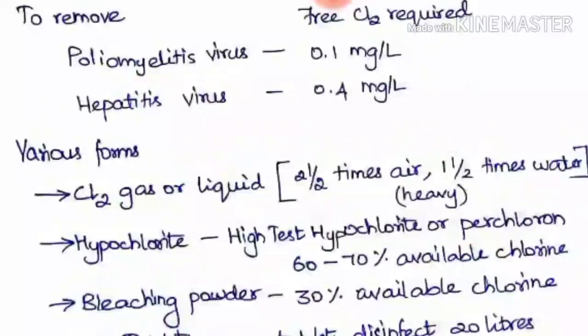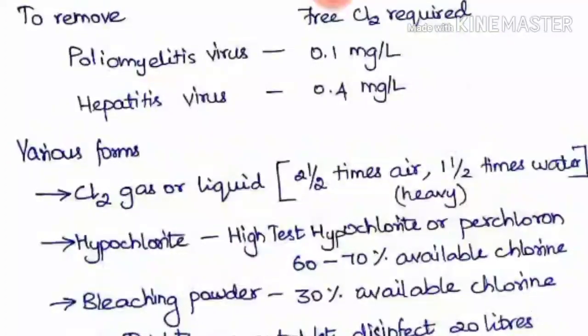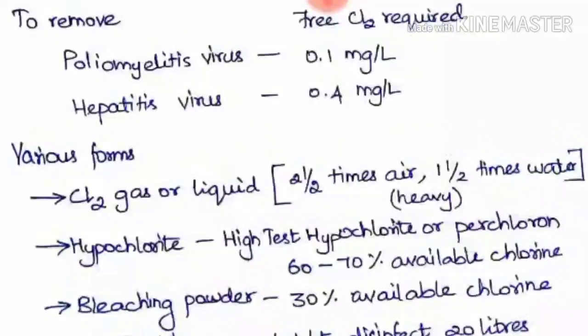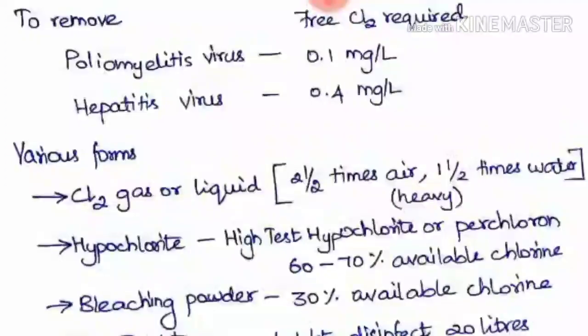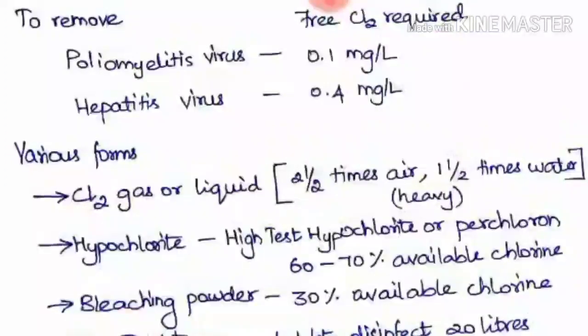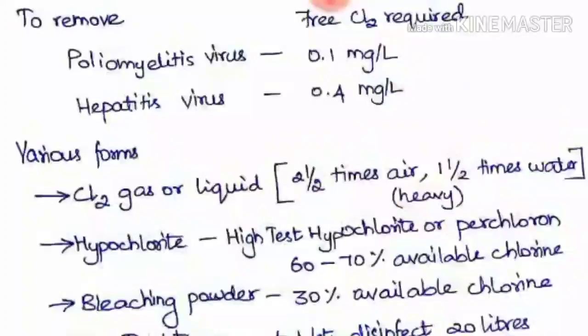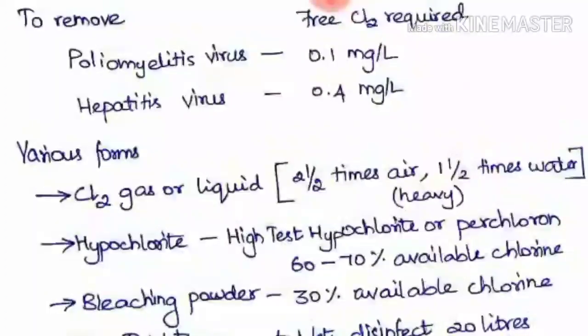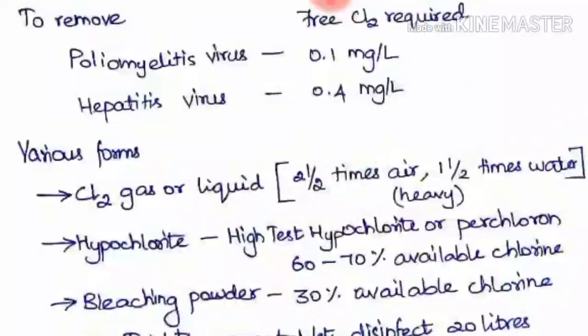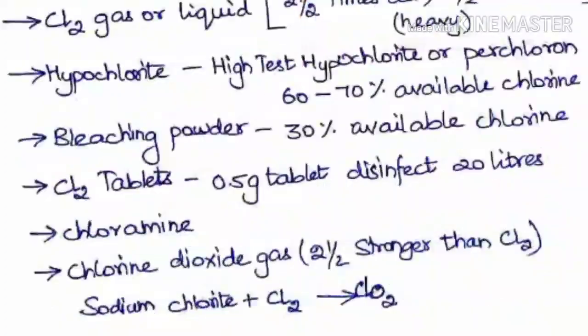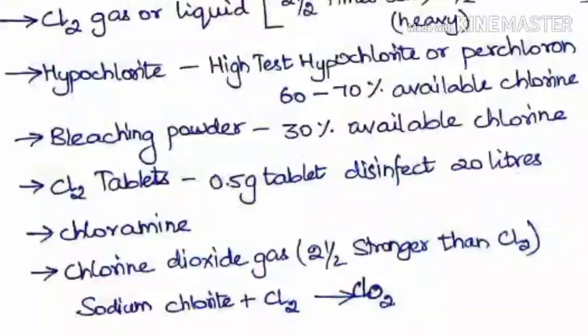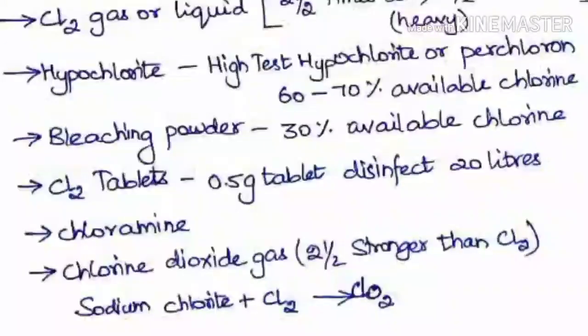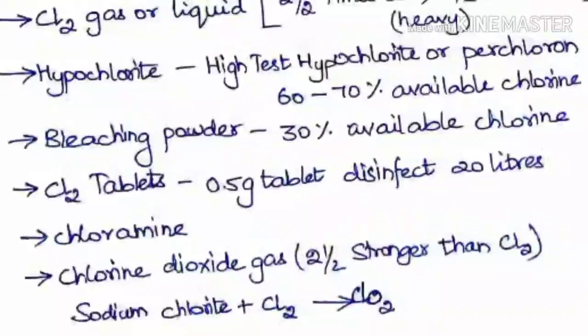Various forms of chlorine can be added. The first is Cl₂ gas or liquid — the gas is nearly two and a half times heavier than air and the liquid is one and a half times heavier than water. The next is hypochlorite, also known as high-test hypochlorite or perchloron, which contains nearly 60 to 70% available chlorine. Next is bleaching powder, which contains nearly 30% available chlorine.